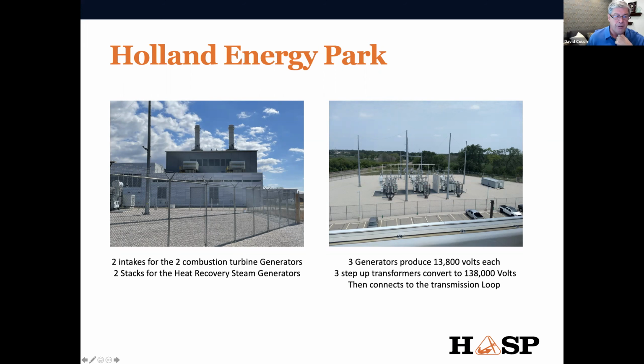If you turn around here and look to the north of the rear of the power plant, you'll see three of those large transformers we talked about earlier. The energy comes out of the generators at 13,800 volts, and these transformers crank it up to 138,000 volts, and off it goes to the transmission environment.